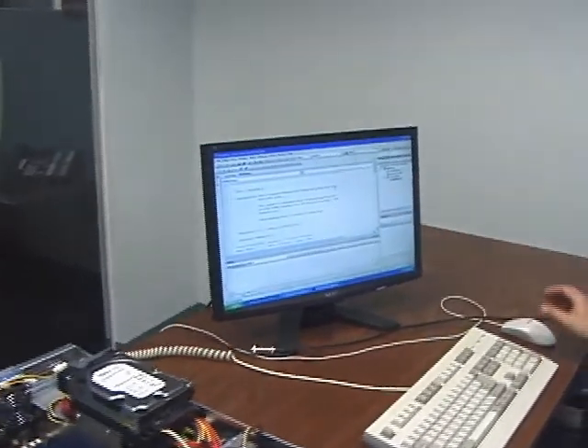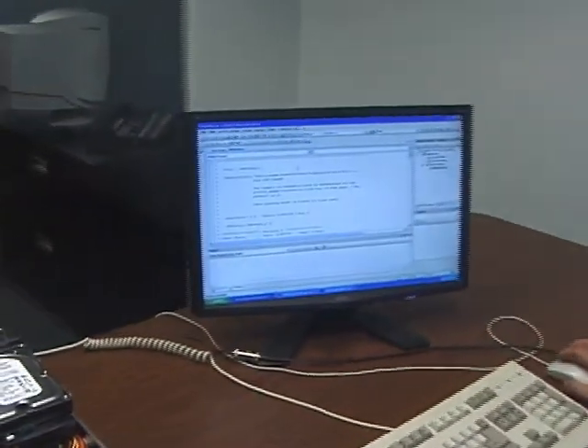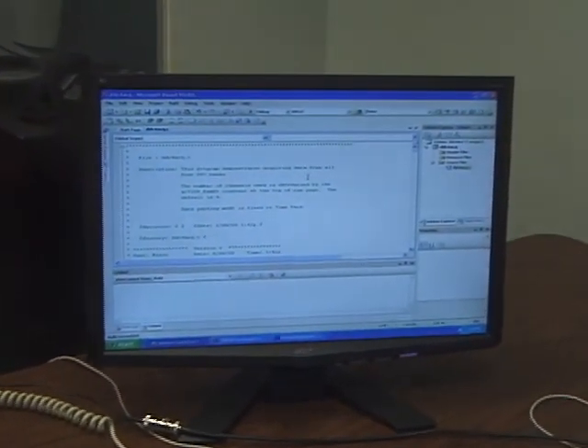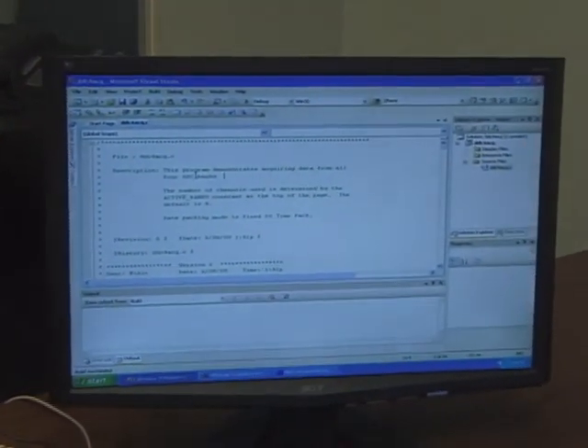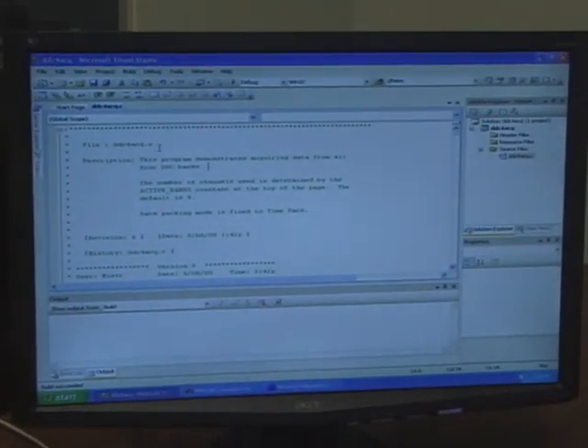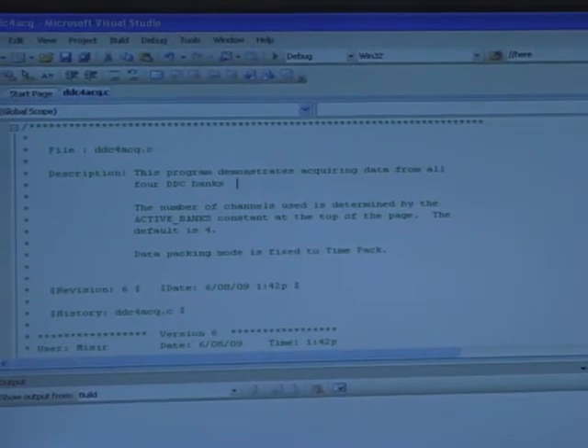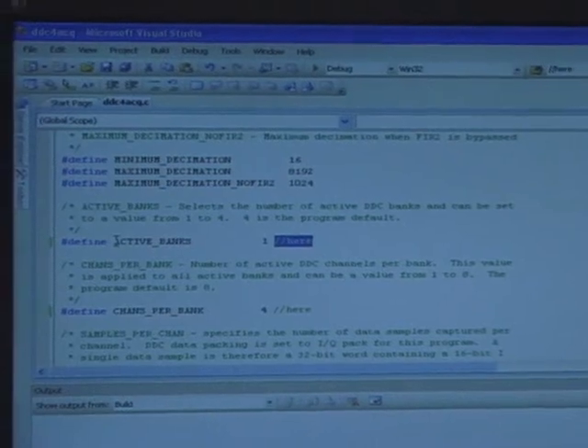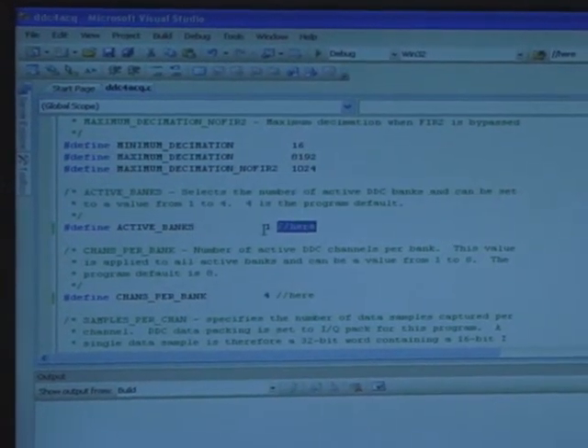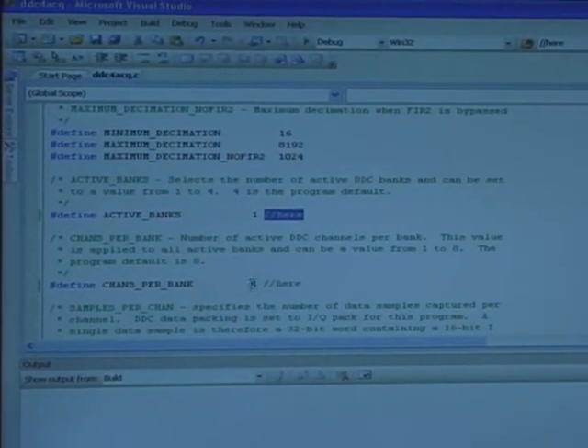Now I'm going to go and show you the software. ReadyFlow software comes with several examples. The example that I chose is DDC4ACQ, and this allows you to program multiple channels per bank and multiple banks. I've set this up so that we have, at least for this demonstration, one active bank and four channels per bank.